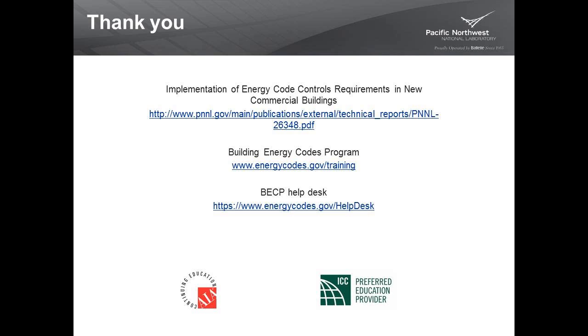Okay. It's encouraging that the commissioning agents had a pretty good idea of the implementation of controls, even though they didn't have empirical data. What 2 or 3 things would you recommend be done to increase configuration of controls? I think it would be good if engineers and building owners built code compliance into the commissioning scope of work so that they actually check the controls for those code-required sequences. If they did that, the commissioning agents would check it. There's no doubt about that, and they were clear about that.